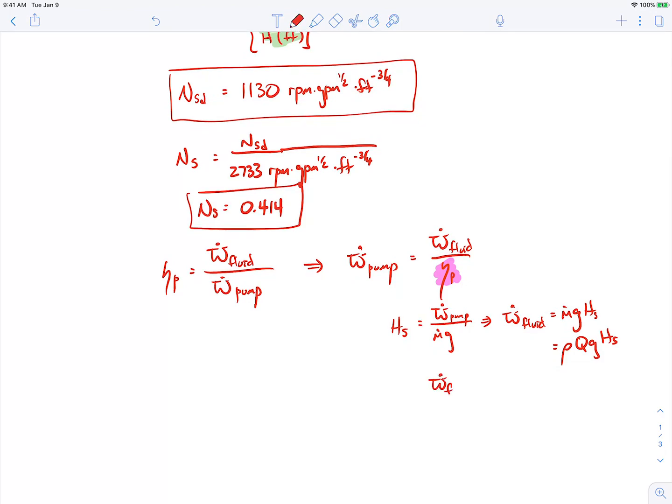There's some unit conversions involved, so you'd have to work through that. I won't do those here. But with English units, you're going to have to do some unit conversions. But if you work through the numbers, you'll get that the power that makes it into the fluid is 8.8 horsepower, which means the power they have to put into the pump comes out to be 11.6 horsepower. It's a little bit more because of the inefficiencies we've discussed. All right, I think that's all there is to this example, so we'll end it there.